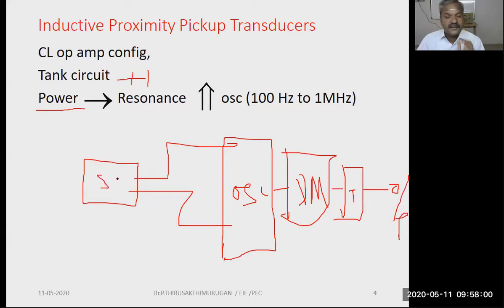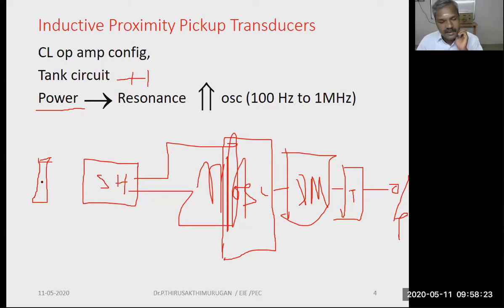So the sensor head here, inductive proximity pickup, we have 2 types of sensor head, shielded and unshielded type. When there is no object nearing the sensor head, more oscillations are generated by the oscillator. When a metal object, basically ferrous metal objects, approaches the sensor head, it suppresses the oscillation. Think like this: when the object is on the sensor head, there won't be any oscillations at all. So using this oscillation frequency of the oscillator, we can detect the range of the sensor.